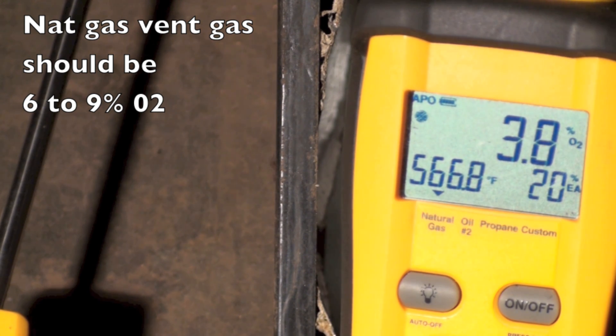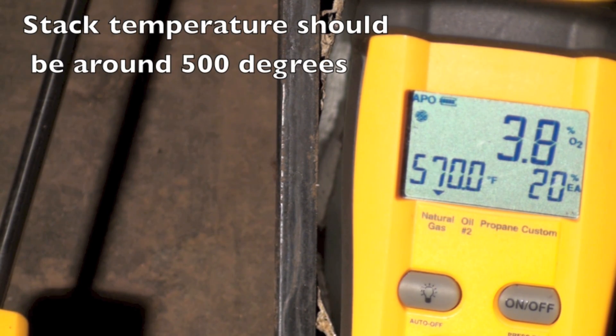Okay, the oxygen is 3.8%. Below that, on the left, you've got the stack temperature, which is about 570.